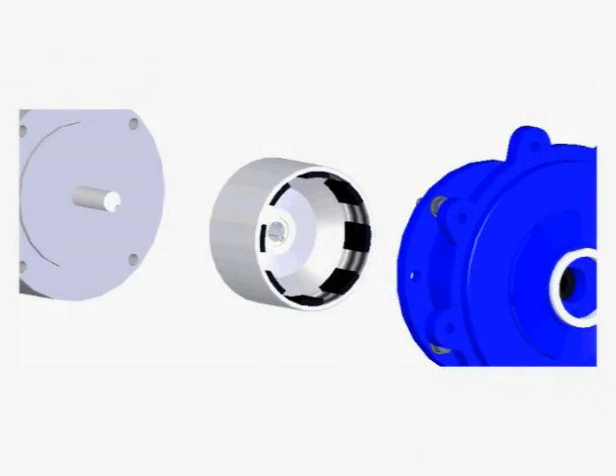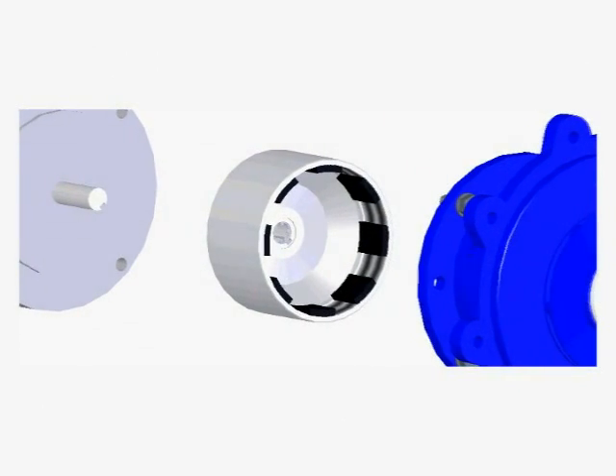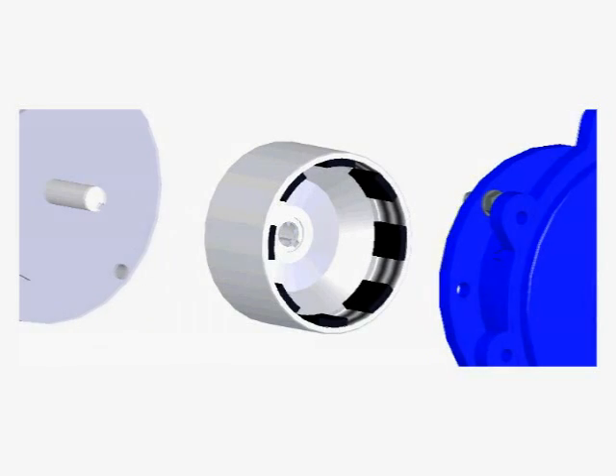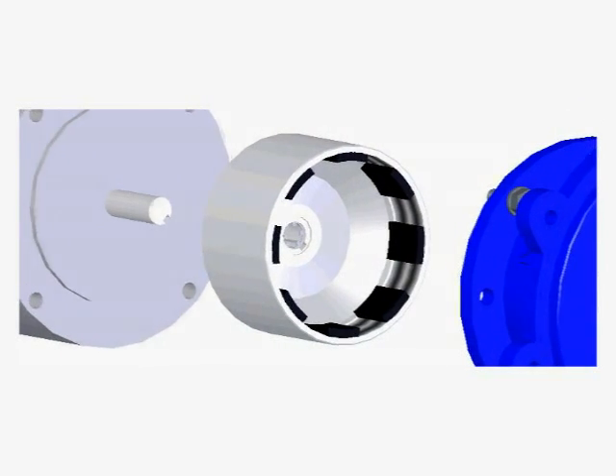Multiple magnetic pole options are utilized to match motor power and allow the pump to handle fluids with specific gravities over 1.8 without impeller trimming. Each outer drive is dynamically balanced to G2.5 to ensure smooth and quiet operation. The DB series' unique easy set outer drive feature makes installing the pump on a motor quick and easy.